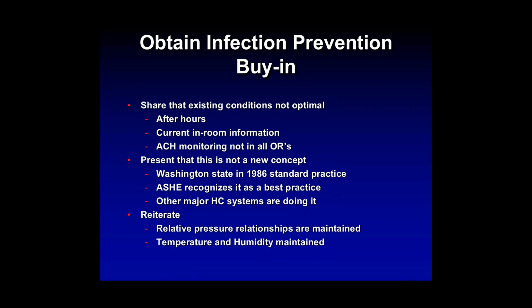our design team felt that if 20 air changes were good, then 25 is probably better. And then being facilities and cautious, they'll set it for 30. And as you get that balance report, you'll find rooms as high as 35. So we did some calculations and found out that if we set it back to the ASHRAE standard, we would save about $250,000 just on the main campus.